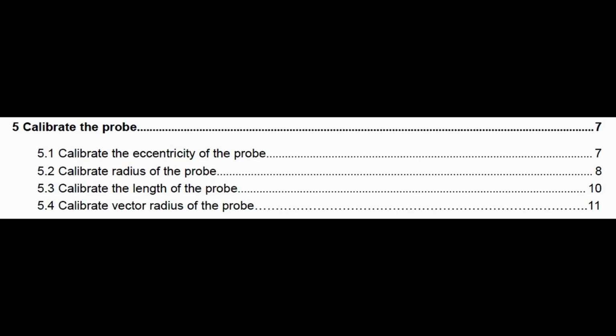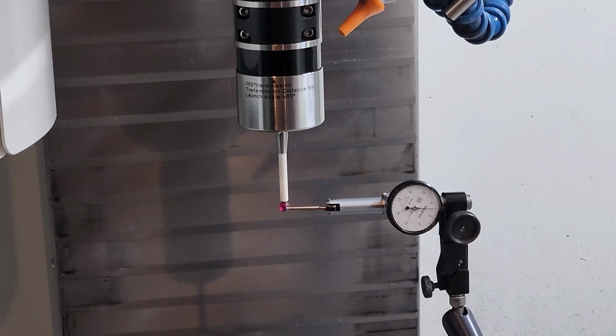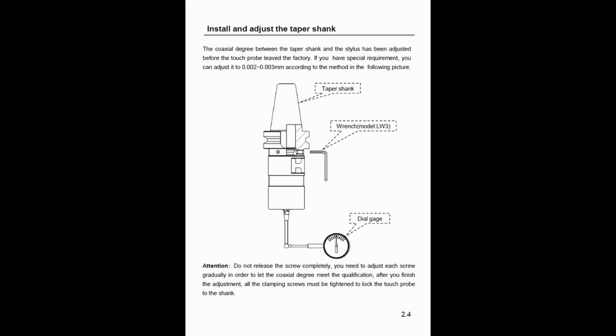There are 4 calibration routines outlined in the manual. These routines calibrate the eccentricity, the radius, the length, and the vector radius. Before calibrating the probe, it's a good idea to verify the run out with the probe and the spindle. Additionally, after replacing the stylus, the run out should be verified and adjusted as needed. According to the manual, to achieve the highest accuracy, the probe should have between 0.002 and 0.003 millimeters of runout. That's about 1/10,000th of an inch, 0.0001. The manual also states that the OP-510 probe is adjusted at the factory to that specification.